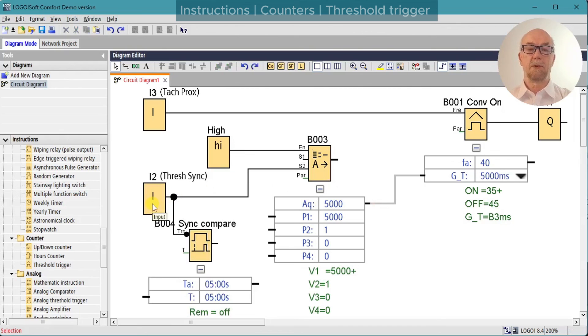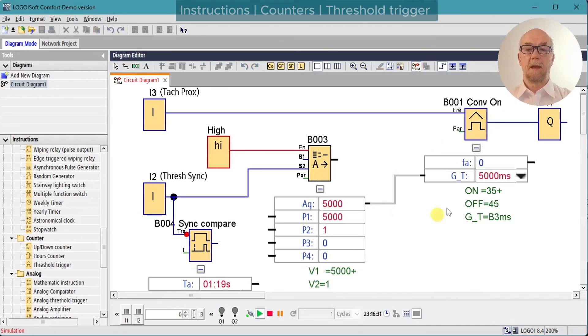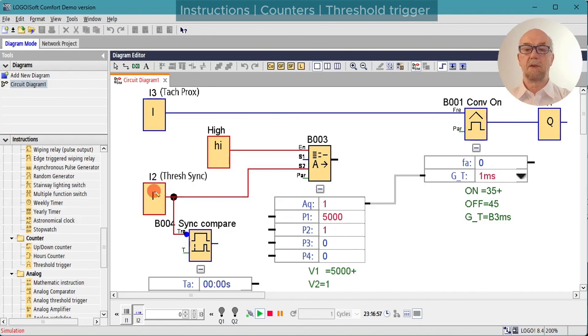I've configured input 2 to run S2 and added a timer so we can watch the timing. Running the simulation, with input 2 off, selector 2 is off and we're feeding the 5000ms value to the gate timer. When we select input 2, parameter 2 is output to the gate timer, effectively holding it off. Releasing input 2 returns us to 5000 milliseconds and the timer starts again.